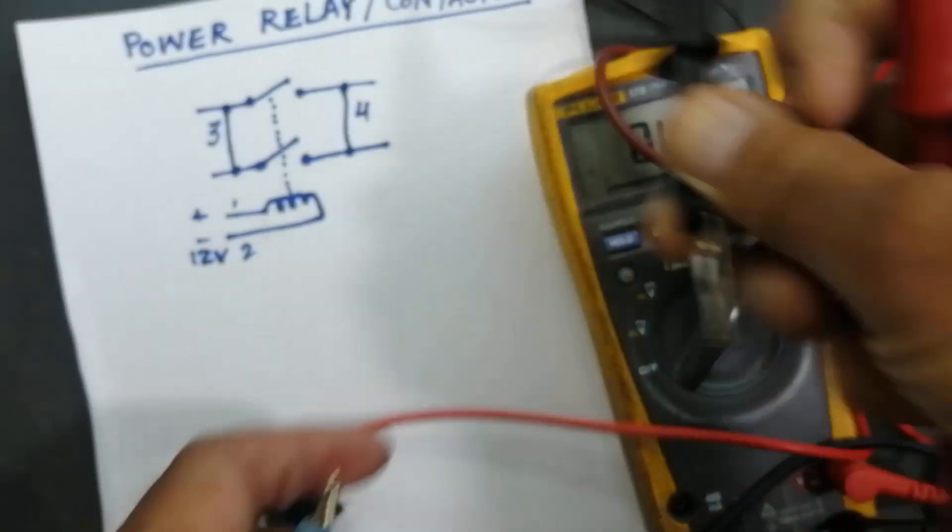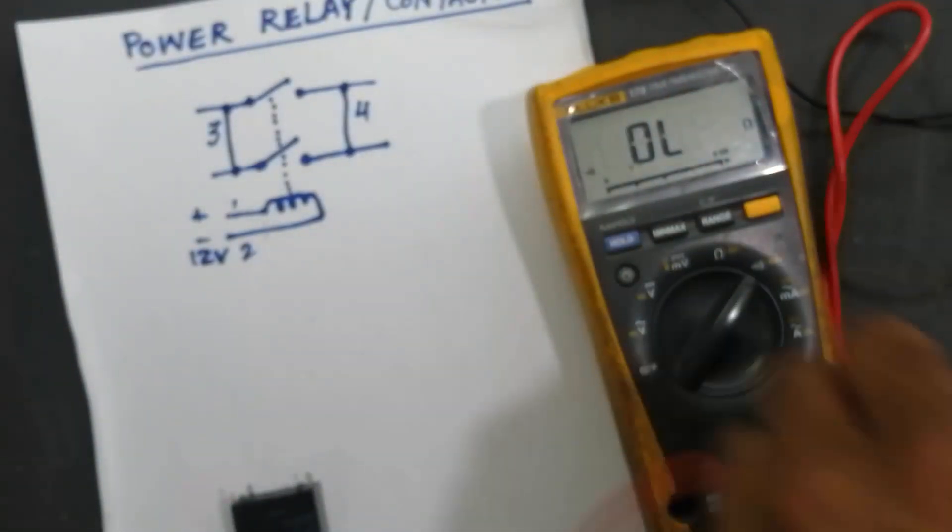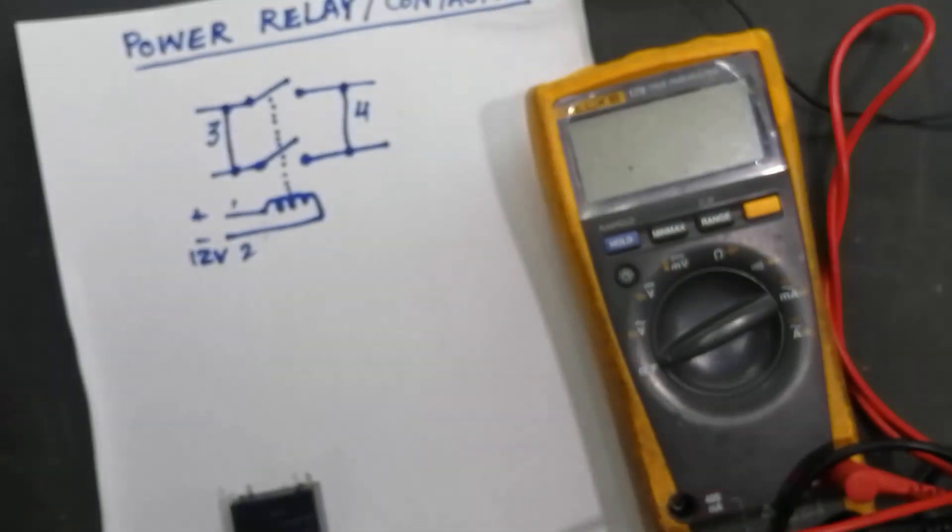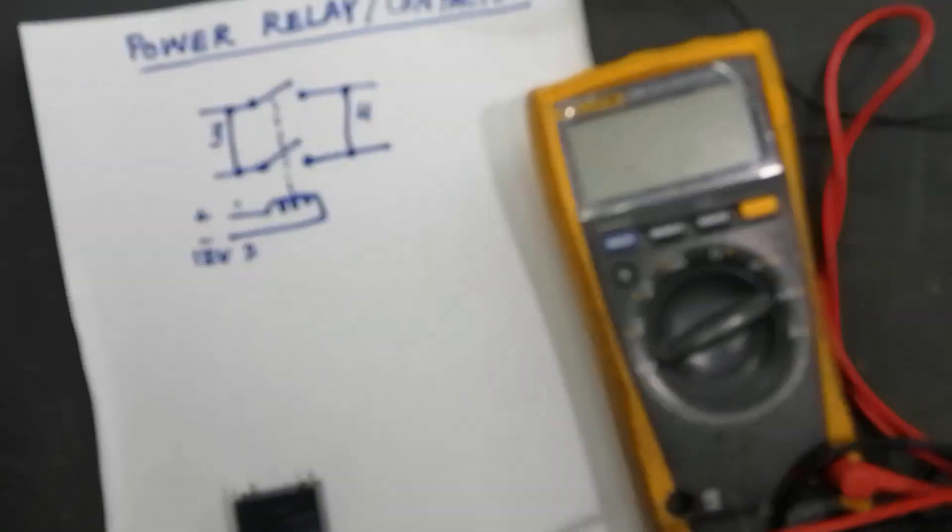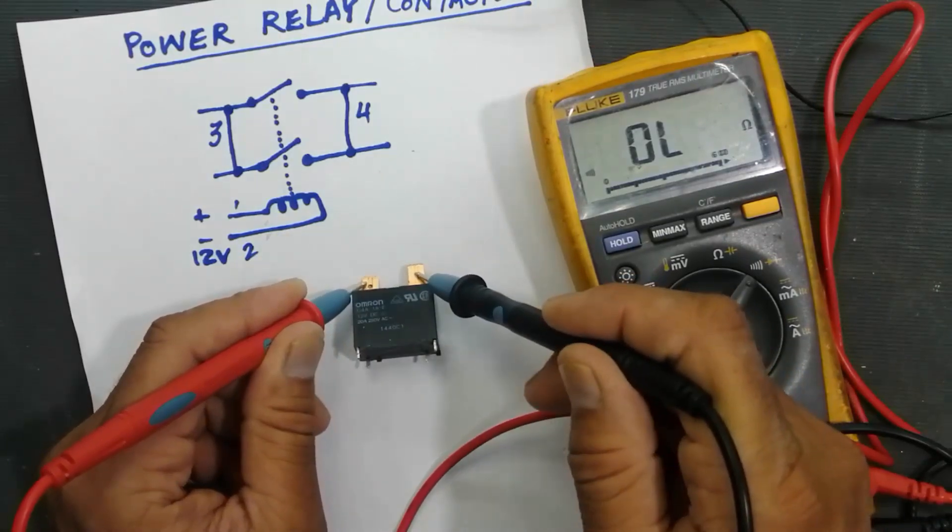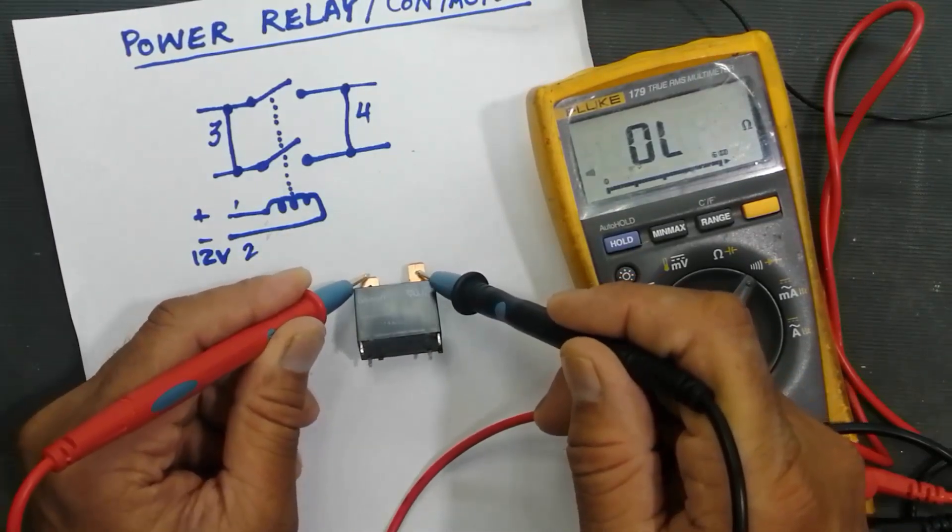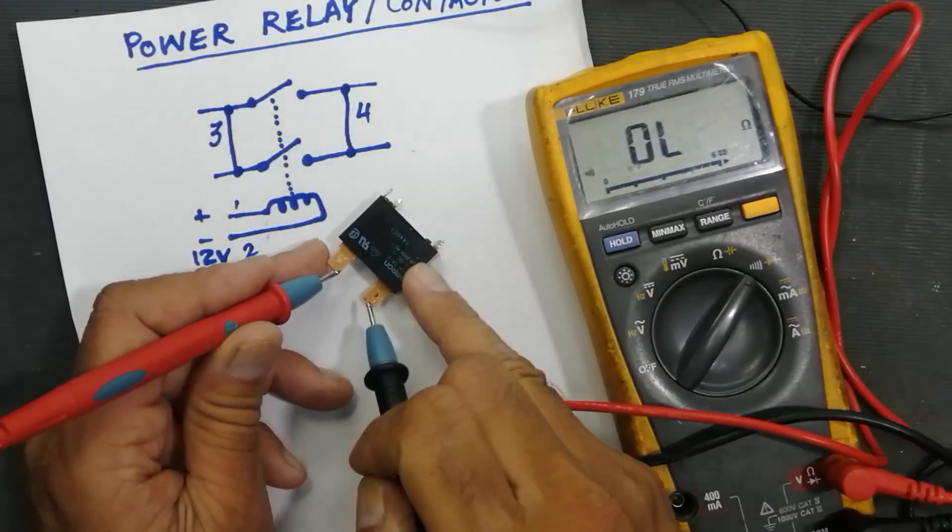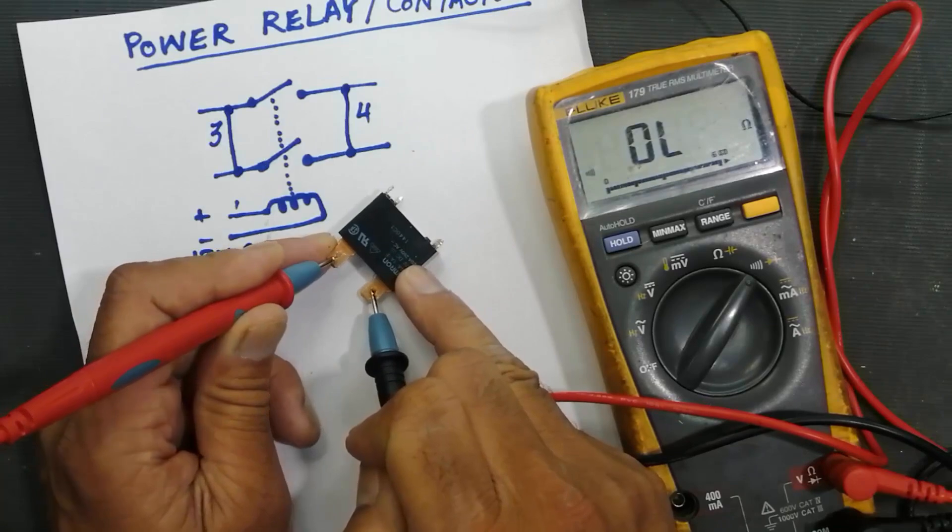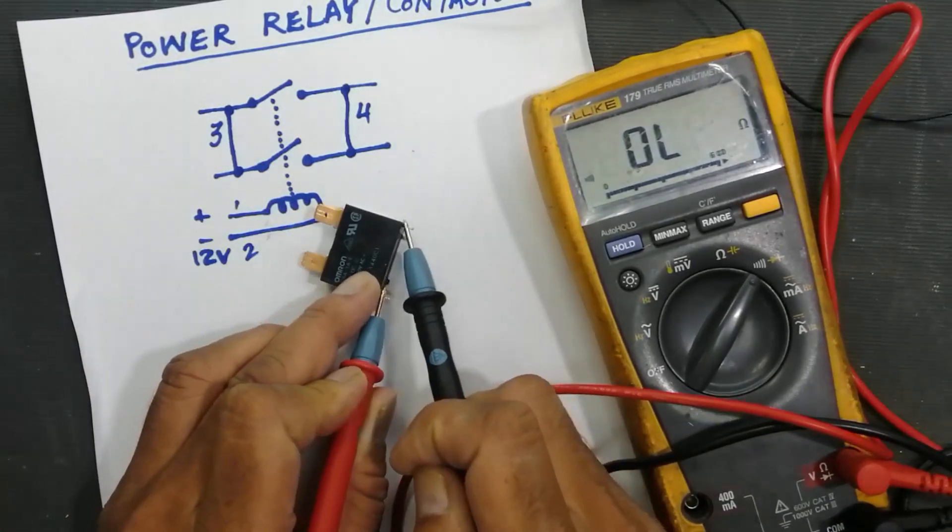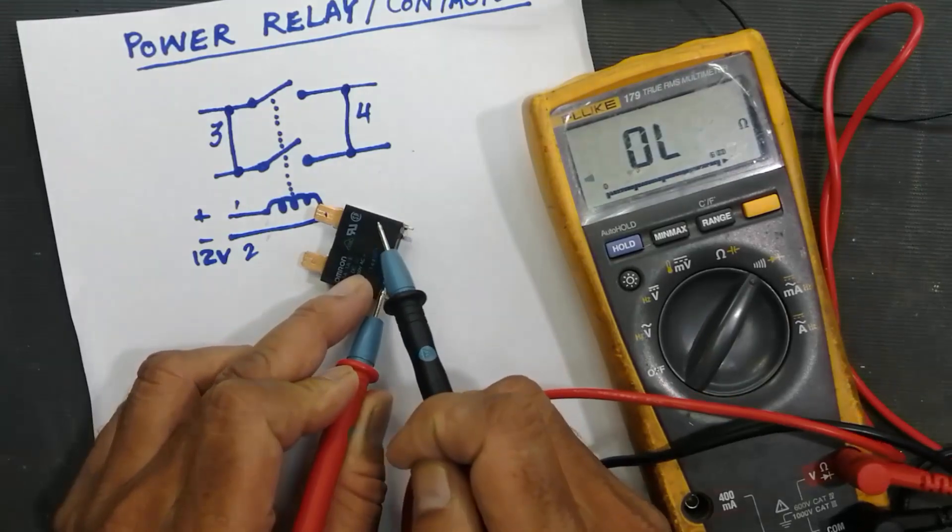So if it is tested in this way that means the relay is good. If it does not give continuity, or if it gives continuity directly at these two points without applying coil voltage or control voltage, that means the relay is short internally. Or this point gives continuity directly, that means the relay is short internally.